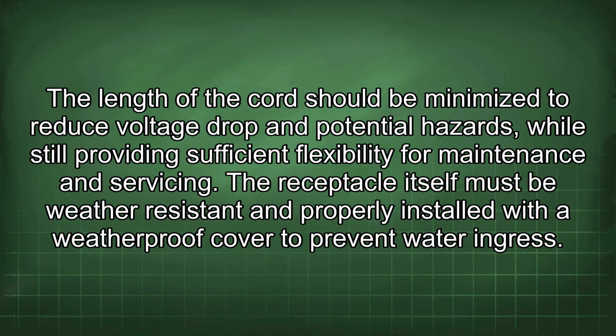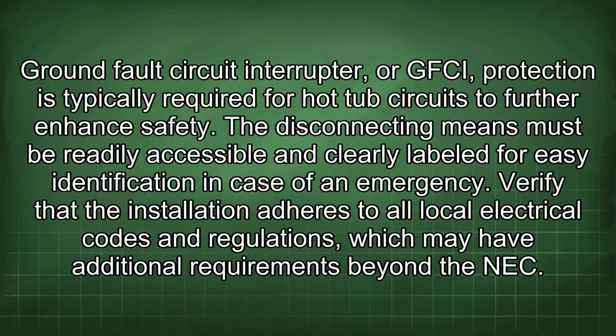The receptacle itself must be weather-resistant and properly installed with a weatherproof cover to prevent water ingress. Ground fault circuit interrupter, or GFCI, protection is typically required for hot tub circuits to further enhance safety. The disconnecting means must be readily accessible and clearly labeled for easy identification in case of an emergency.